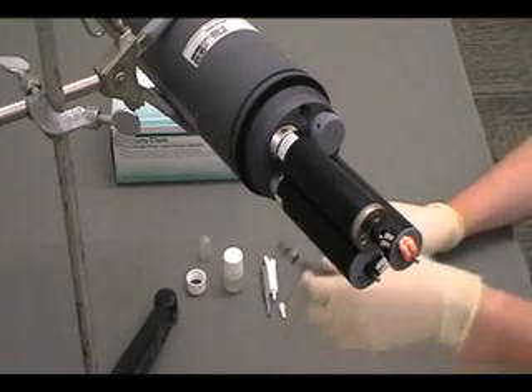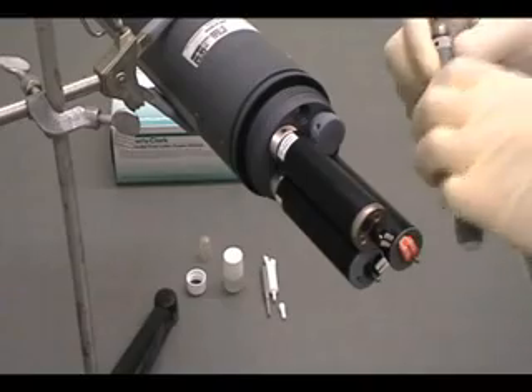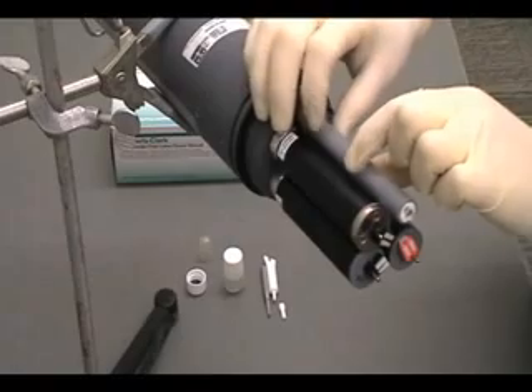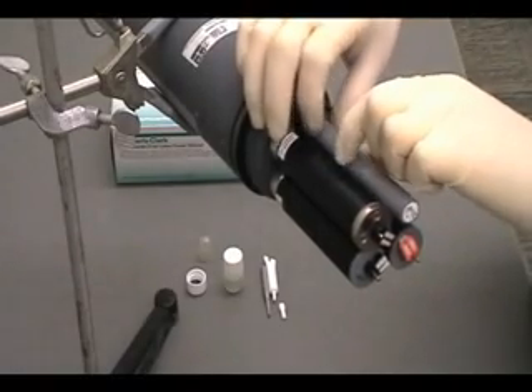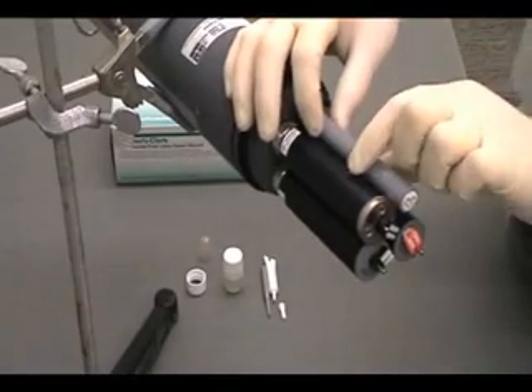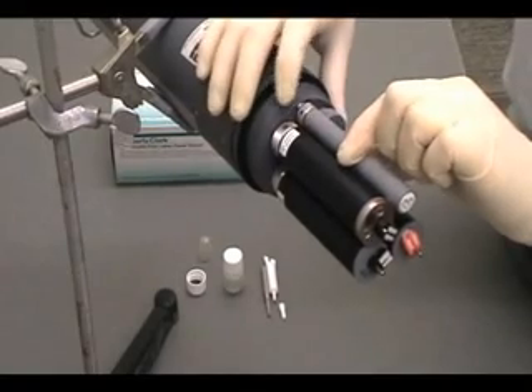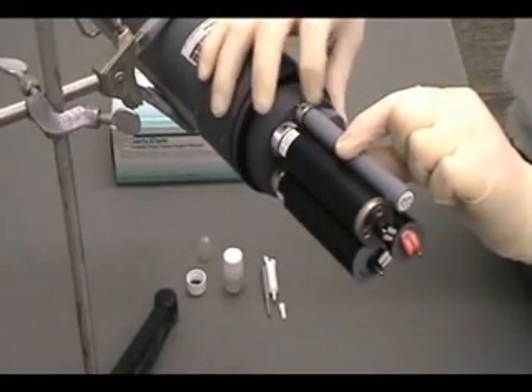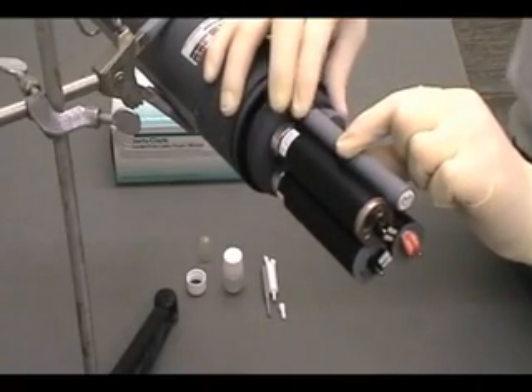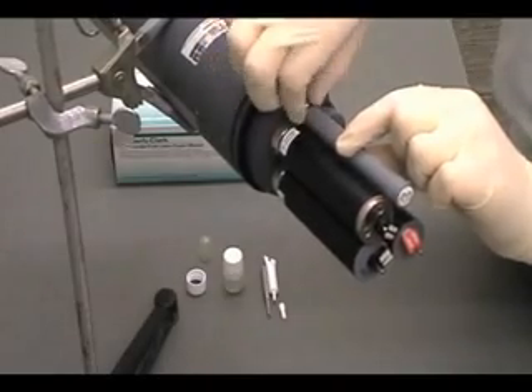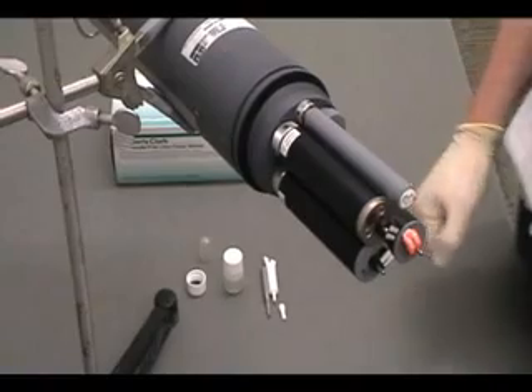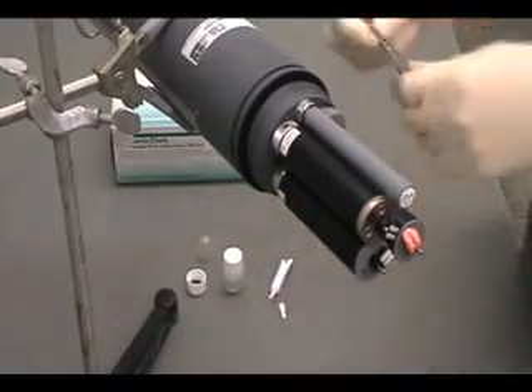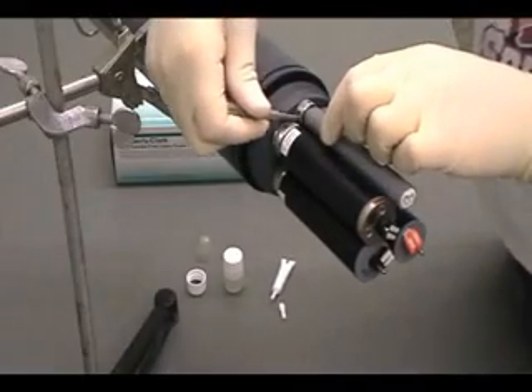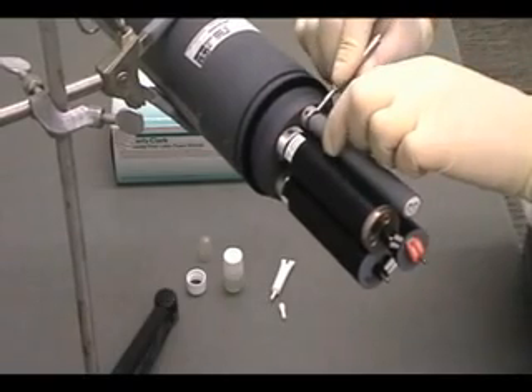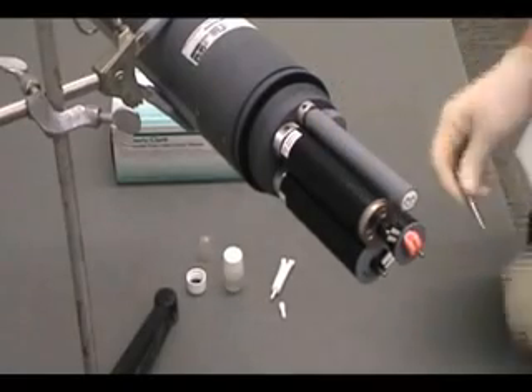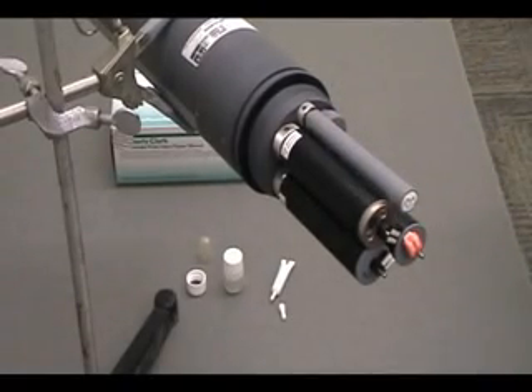Insert the sensor into the appropriate port, in this case the 4-pin port, and gently rotate until the pins of the connectors are aligned. Push the sensor inward so that it seats in the port snugly. Slowly finger tighten the nut down toward the bulkhead. During this step, be careful not to cross-thread the nut. If you meet resistance while finger tightening, stop, back out, and begin the process again. Use the long end of the installation tool to tighten the nut an additional quarter turn until snug. Do not over-tighten. When tightened properly, there should be no space between the nut of the regular sensor and the body of the bulkhead.